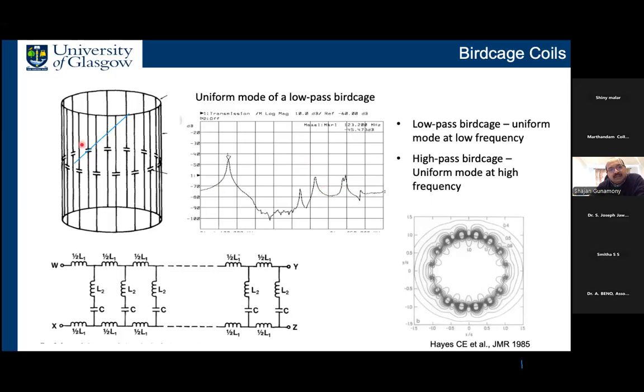So suppose we have a coil with n rungs, you would measure n minus 1 modes. That means if you have a birdcage with 8 rungs, you will measure 7 modes. Modes in the sense they are all these frequency peaks. And for a low pass birdcage, the most interesting for us is the lowest frequency. That's called the uniform mode, where we produce a uniform magnetic field. So if you want to build a coil for low frequency, then you have to choose a low pass birdcage because the uniform mode is the lowest frequency. In the same way, if you want to build a coil for high frequency, then we have to choose a high pass birdcage because the uniform mode is the highest frequency.